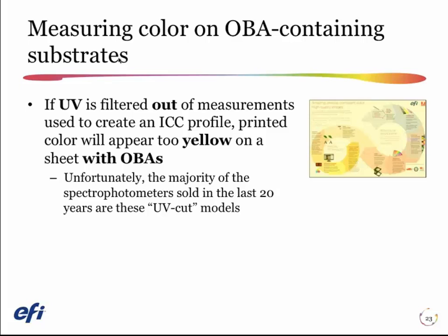Your light booth before 2009 also didn't have any ultraviolet light in it, so the sheet wouldn't glow in the booth. You didn't measure the glowing in making your profile, and everything worked very well. 2009, things got more complicated. Because the ISO added UV to the specification for the light booth, now if I measure a sheet that has optical brightening agents with a UV cut, a filtered spectrophotometer, I filter out all that glow, right? I don't get any of that bluing of the paper in my measurements.